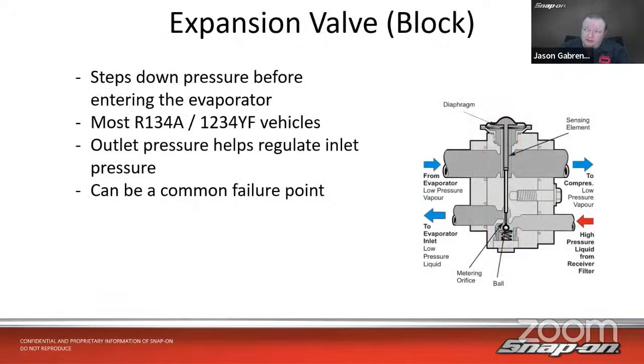So as I said, there's some older technology before this for R12. We're not going to cover that either. We'll cover the expansion valve. So it steps down the pressure before it enters the evaporator. So we don't want high pressure vapor going into the evaporator. So it uses a diaphragm and a sensing element to kind of bleed off some pressure. When high pressure comes in, we got the little orifice that meters it, and then it allows low pressure liquid out. So high pressure liquid in, low pressure liquid out, and then a low pressure vapor from the evaporator goes out, and then it goes out as a low pressure vapor to the compressor. So it comes in as high due to this metering orifice and the ball there. The liquid goes down to a lower pressure, and that's how it drops the pressure. And the outlet pressure, in turn, helps regulate the inlet pressure with the sensing element and diaphragm.